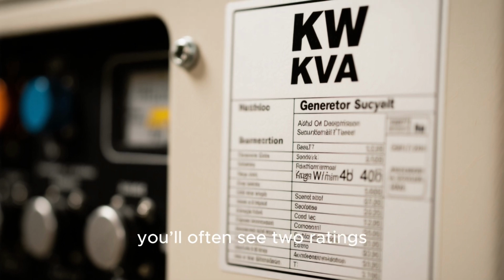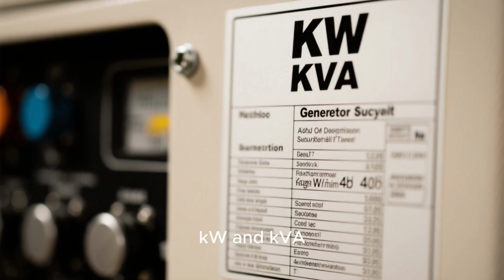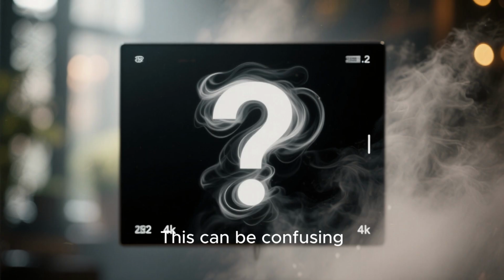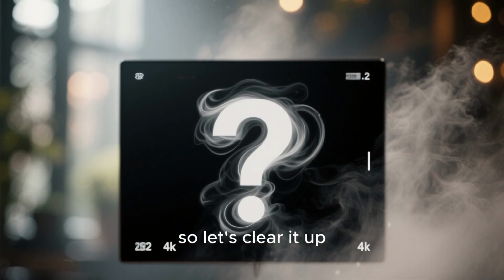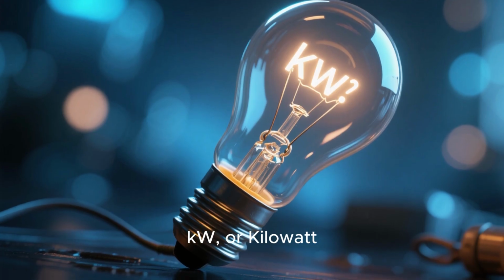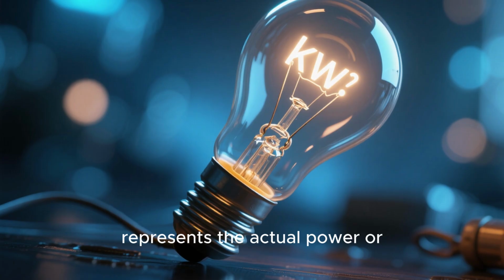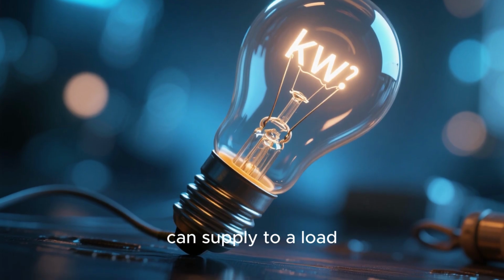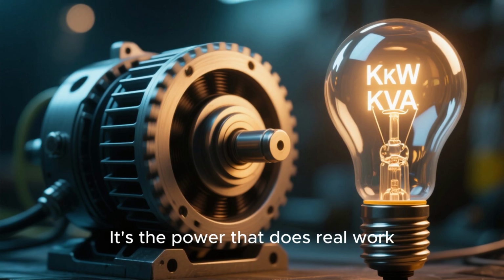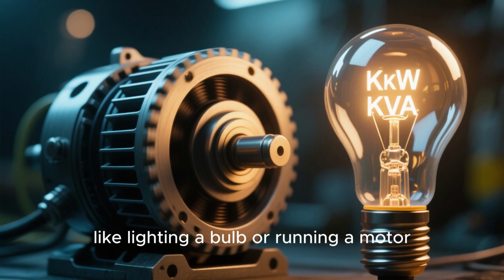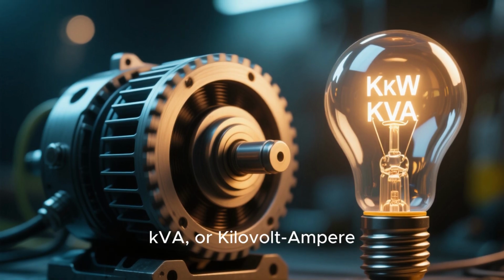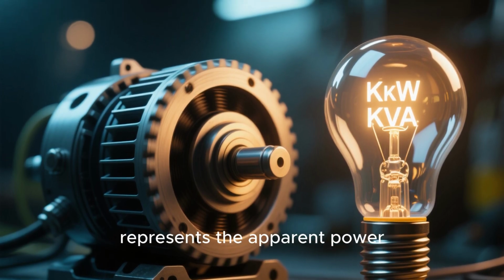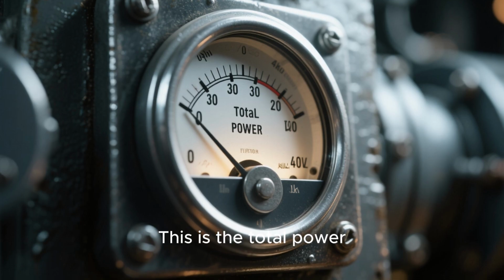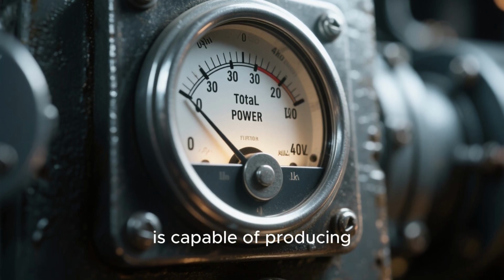When you look at a generator's specifications, you'll often see its ratings, kW and kVA. This can be confusing, so let's clear it up. kW, or kilowatt, represents the actual power or useful power that the generator can supply to a load. It's the power that does real work, like lighting a bulb or running a motor. kVA, or kilovolt-ampere, represents the apparent power. This is the total power that the generator is capable of producing.